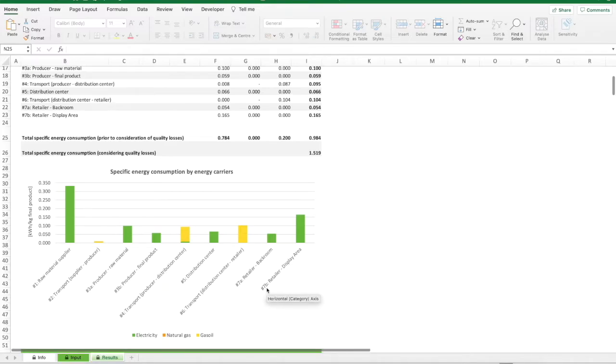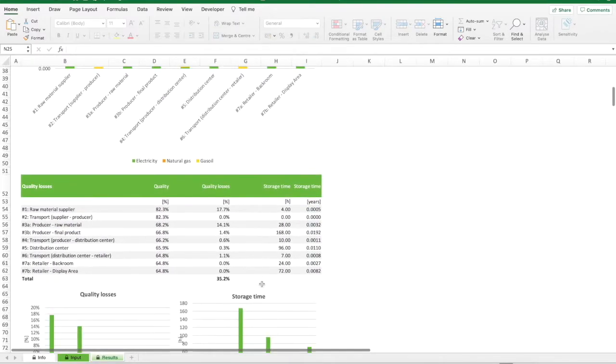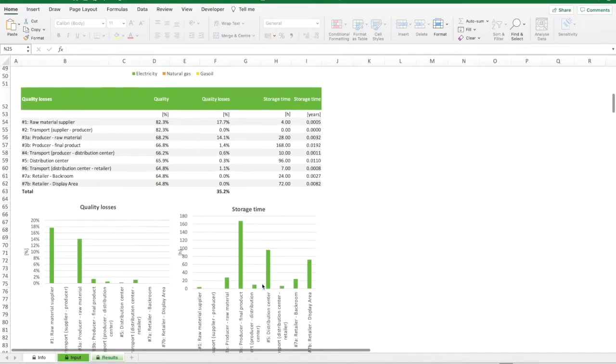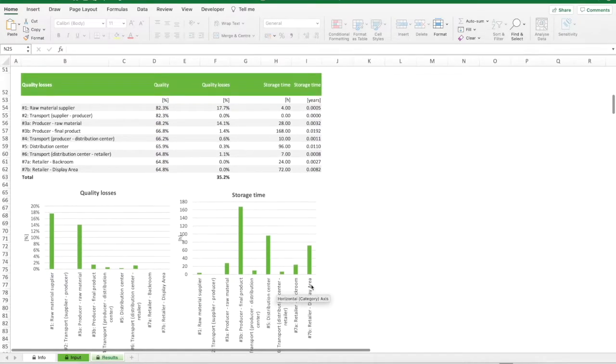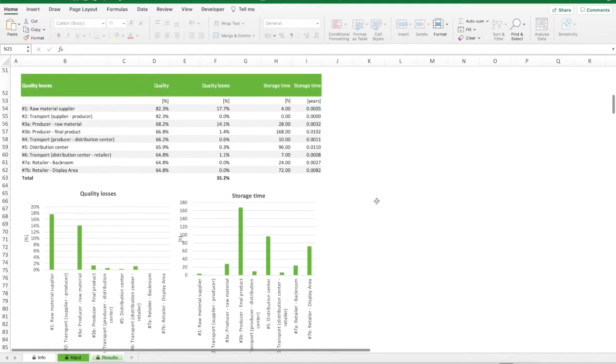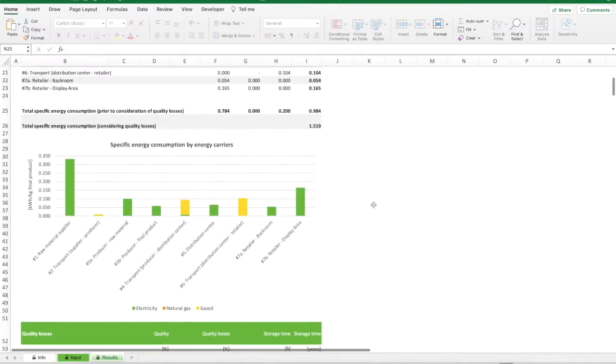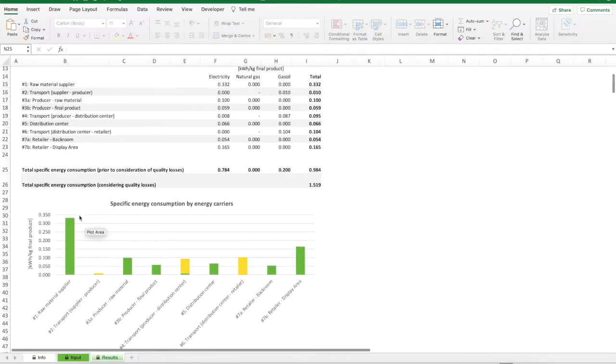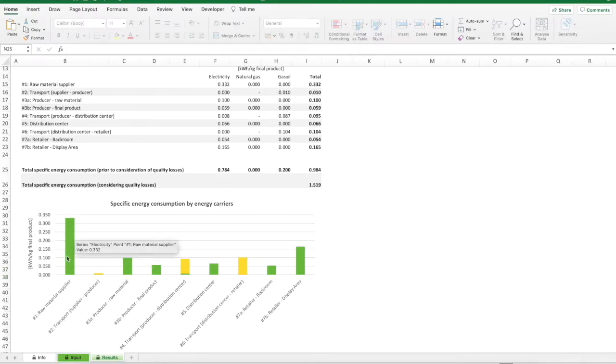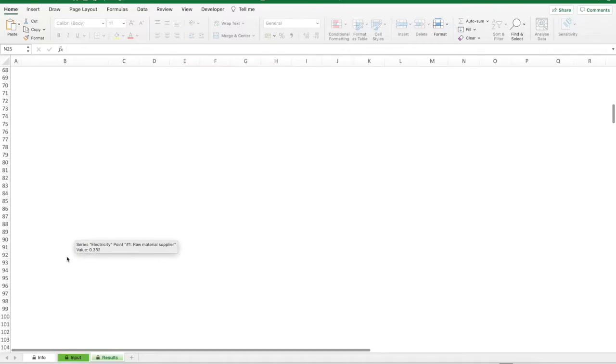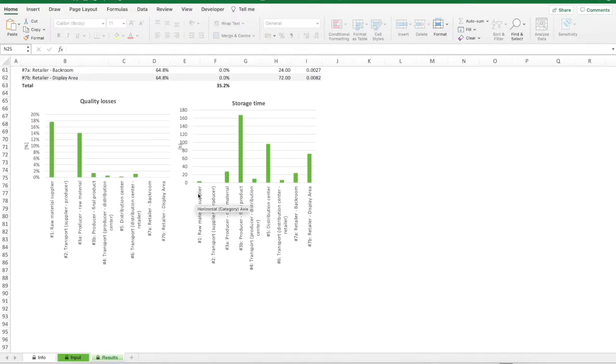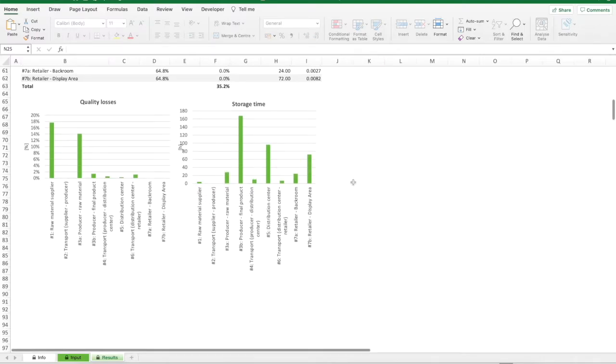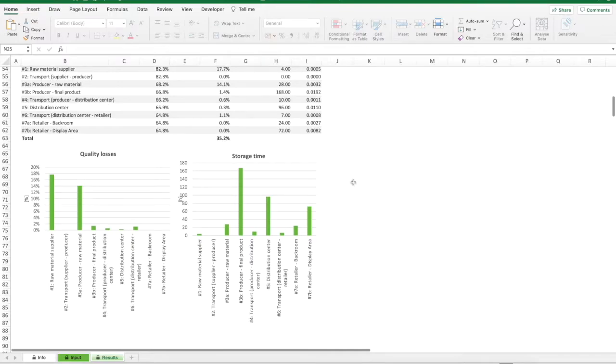At the same time, the results in terms of quality degradation and storage time are hereafter reported. The indicator depicted can support decision makers in prioritizing the intervention in order to improve the energy efficiency of the cold chain. For instance, for the specific case shown in the example it is possible to observe that the warehouse at the raw material supplier is one the most consuming stage and at the same time it is where the highest quality losses occur, even though the storage time is almost negligible with respect to other stages. Hence, the priority in improving energy performance should be given to this stage.